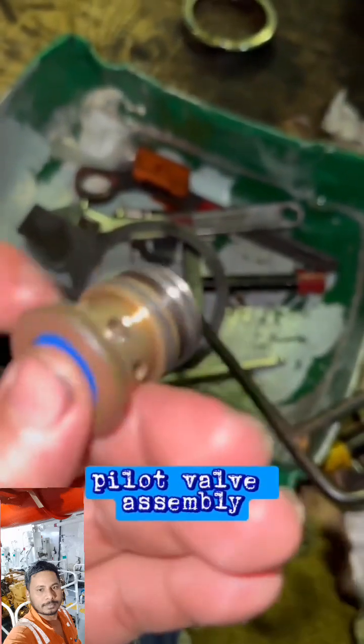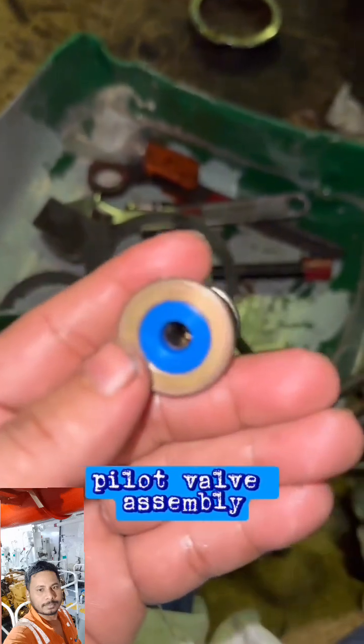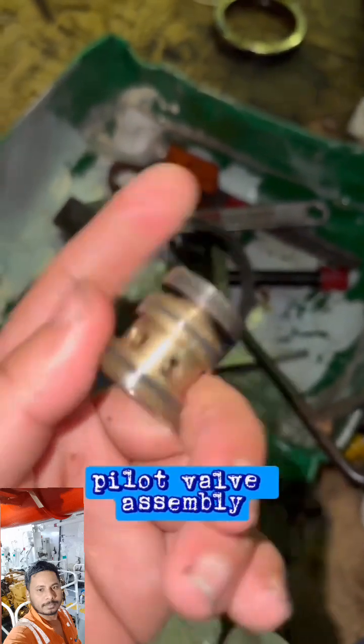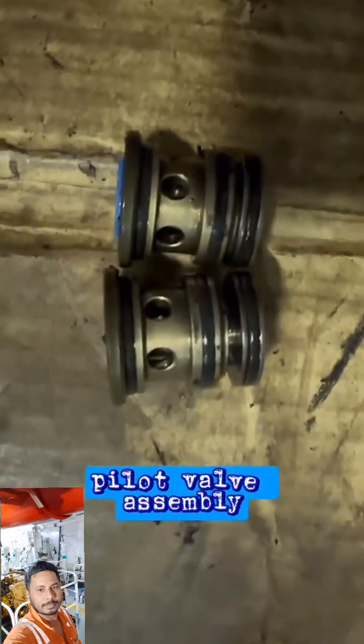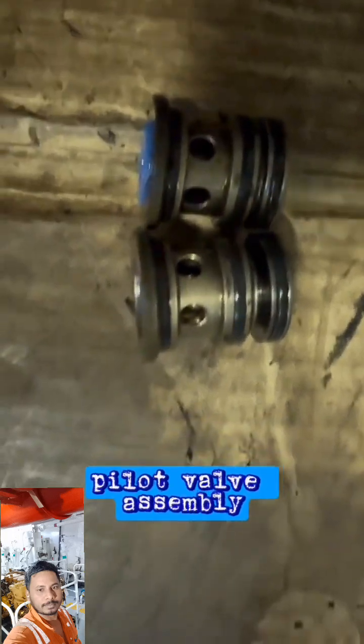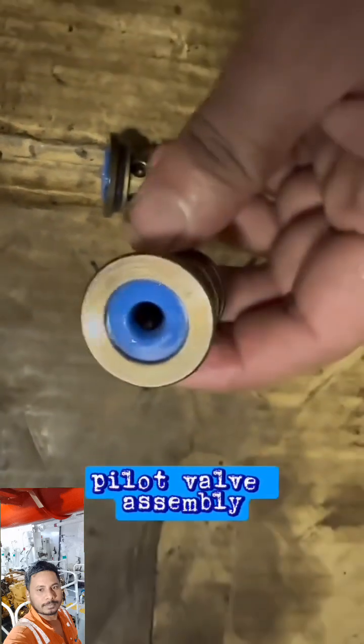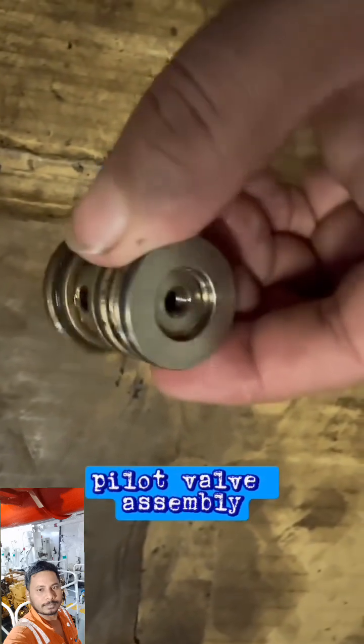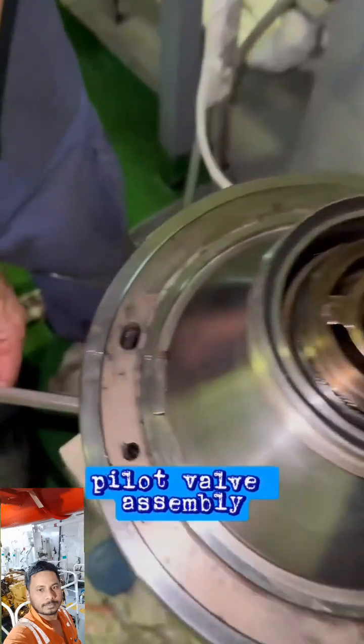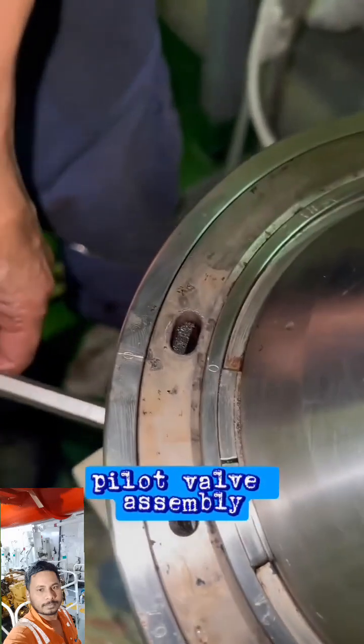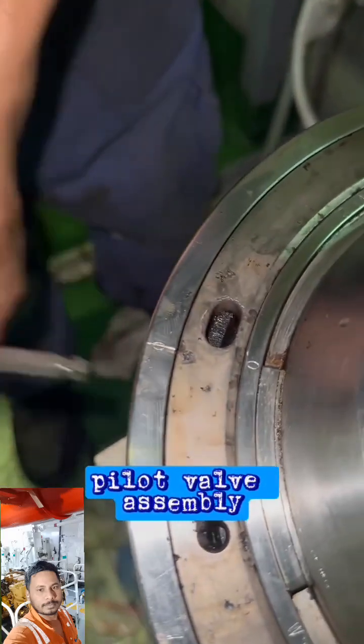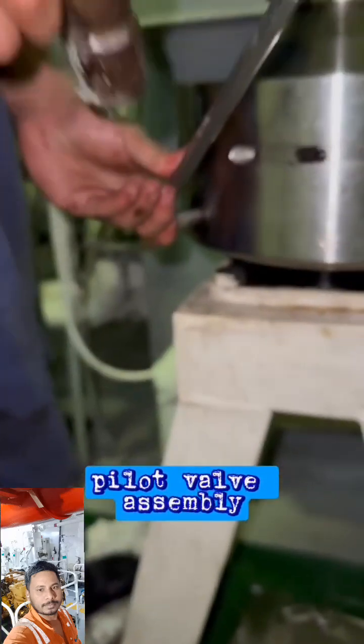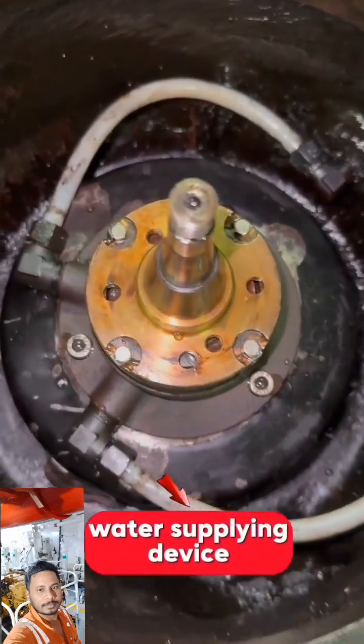Pilot valve assembly, used to direct the operating water, keeping the main cylinder closed or open during operation. The main cylinder closes the bowl when the pilot valve assembly is in closed position. If the pilot valve assembly opens, the main cylinder will slide vertically down, opening the bowl and allowing the discharge of accumulated sludge.